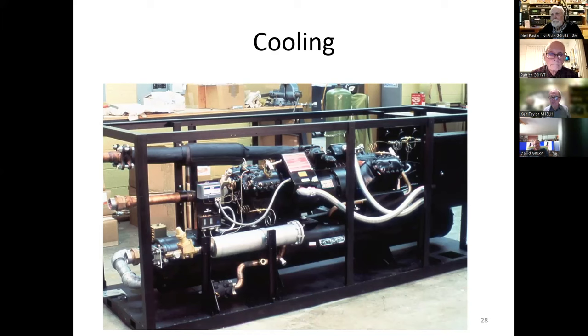This supplied Freon through stainless steel tubes embedded in aluminium cold bars running up the sides of each column. This cooling system was one of the few patents that Cray actually had. The chips themselves attained a temperature of between 48 and 54 degrees, depending on their position in the module. The copper cold plate reached a temperature of 25 degrees when it was clamped to the cold bar, and the cold bar was set to 21 degrees.